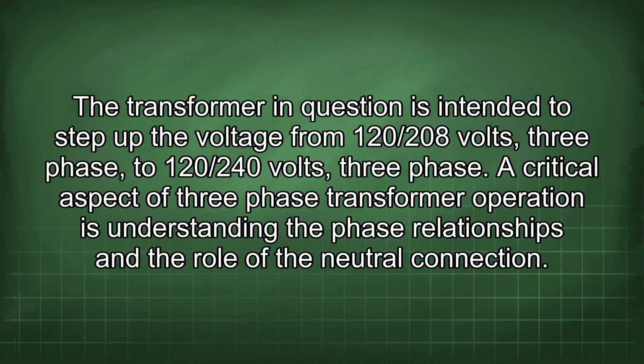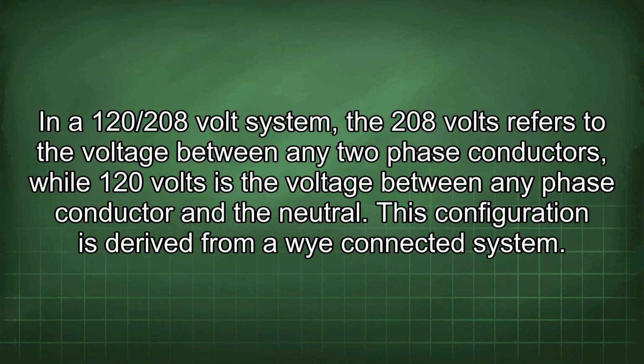The transformer in question is intended to step up the voltage from 120/208 volts, 3-phase, to 120/240 volts, 3-phase. A critical aspect of 3-phase transformer operation is understanding the phase relationships and the role of the neutral connection. In a 120/208 volt system, the 208 volts refers to the voltage between any two-phase conductors, while 120 volts is the voltage between any phase conductor and the neutral. This configuration is derived from a Y-connected system.